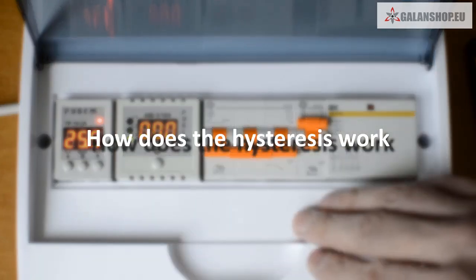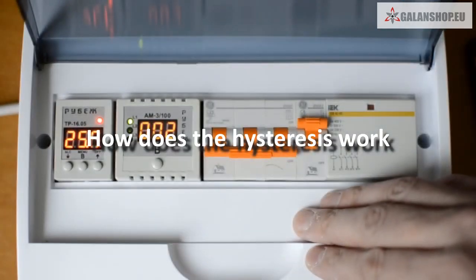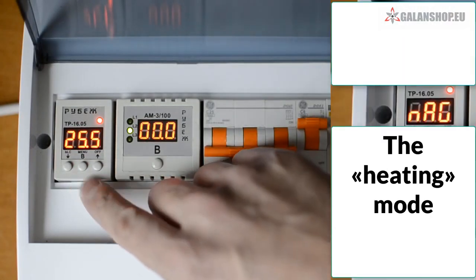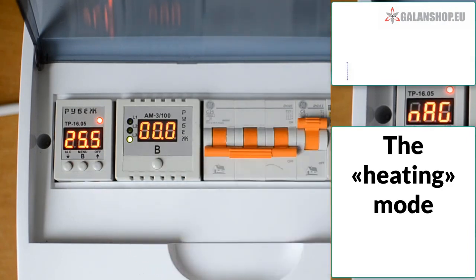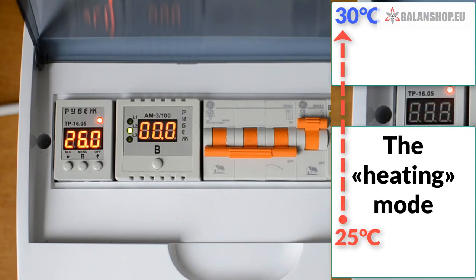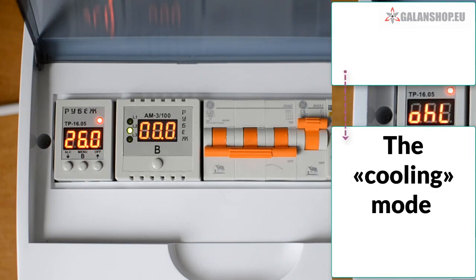How does the hysteresis work? When the heating mode has been selected, the temperature is set to 30 degrees. For example, the hysteresis value is set to 5 degrees. The TR-16 heat regulator will turn the boiler on at the temperature of 25 degrees and turn it off at 30 degrees. Thus, the boiler will work in the temperature range of 25 to 30 degrees.